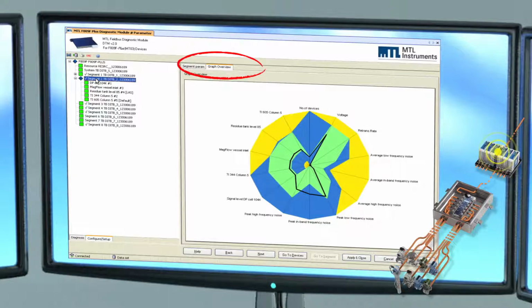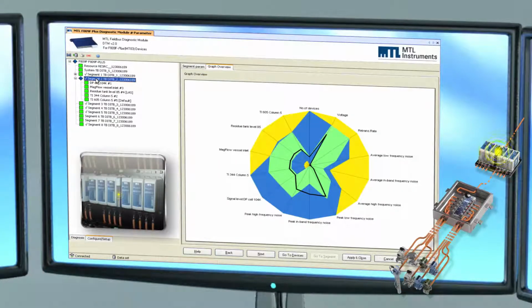The Graph Overview tab in the segment view reveals a graphical representation of the measured parameters for each segment. The black polygon joins the actual parameter on each radial arm of the diagram. For a healthy segment, the polygon remains within the green area to indicate that each parameter is healthy. Note here that the line extends into the blue alert area for the detected in-band noise measurement.